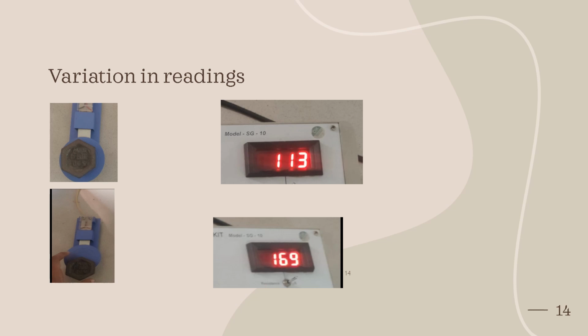Okay, now we can see the variation in readings. In the first diagram, I place the weight slightly away from the center mark, and corresponding to a 1 kg weight, I get a reading of 1.13 kg. And in the second diagram, as you can see, I place the weight very near to the edge of the cantilever beam, and corresponding to a 1 kg weight, I was getting a reading of 1.69 kgs, which says that there is 69% error in the latter, in the bottom diagram, when I place the weight at the edge of the cantilever beam. This shows that the placement of the weight near the cantilever beam center is very important for accurate readings.